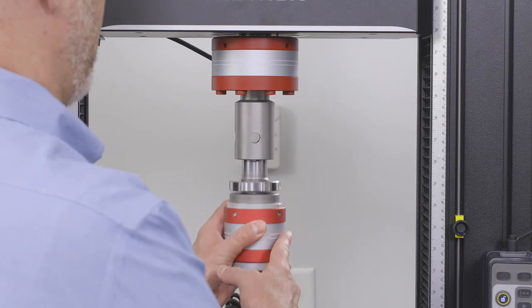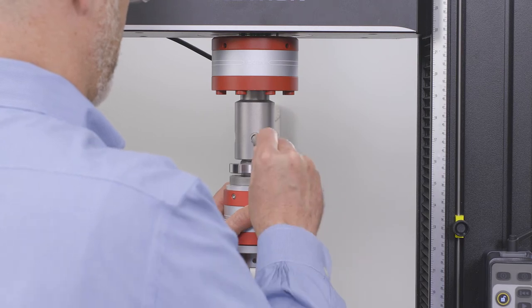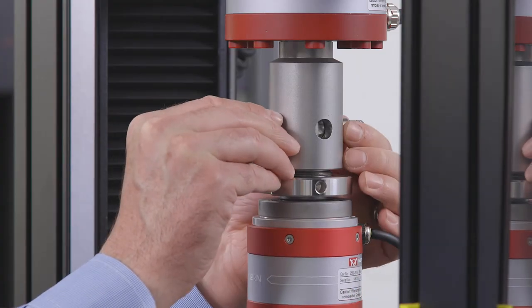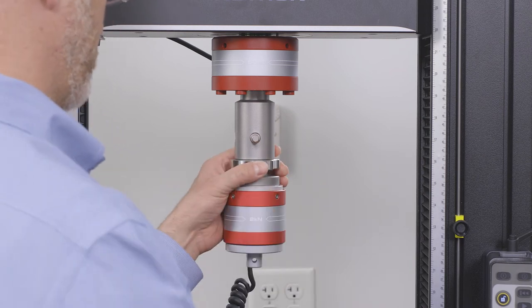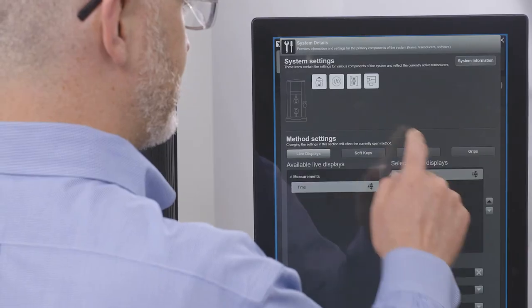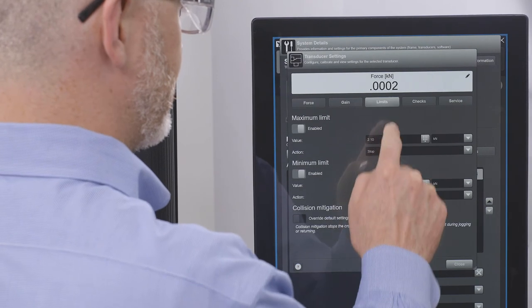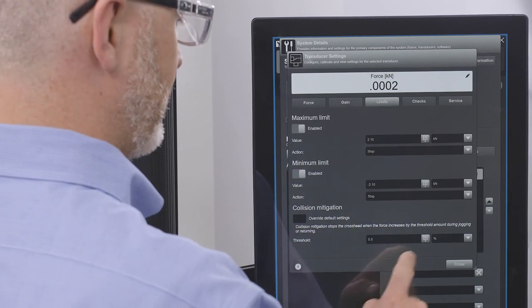Collision Mitigation is always active and cannot be turned off. The sensitivity of its response is tied to the capacity of the load cell. For some applications, a user may want to change this sensitivity. Adjustments can be made in the load cell menu under Limits.